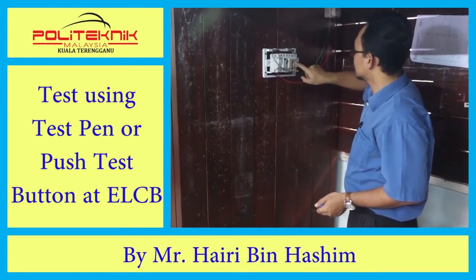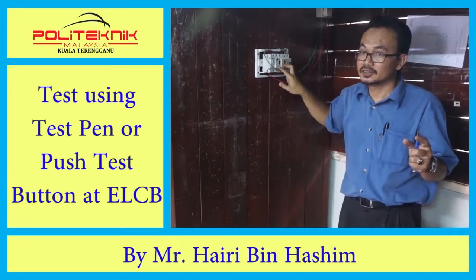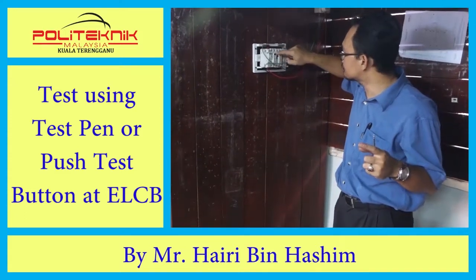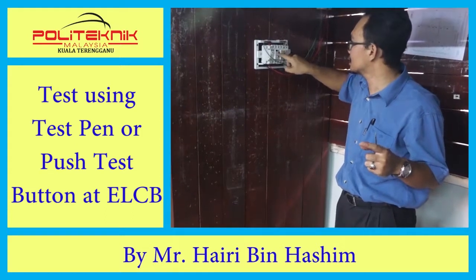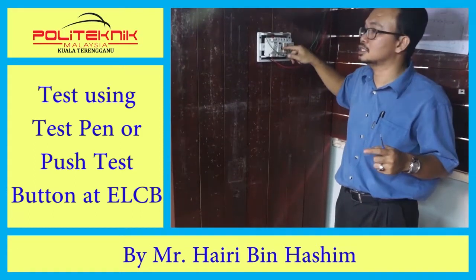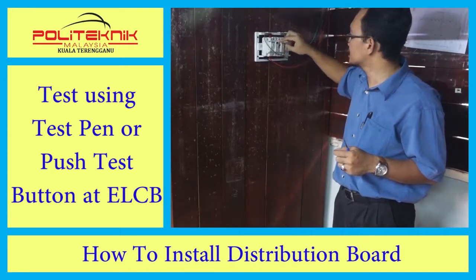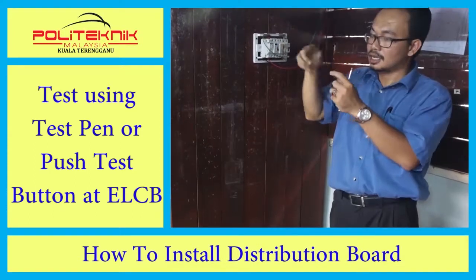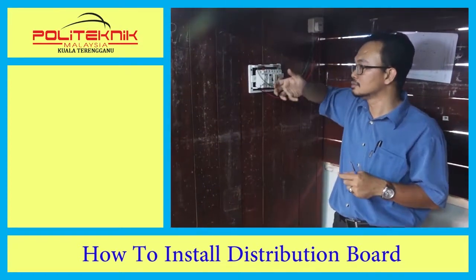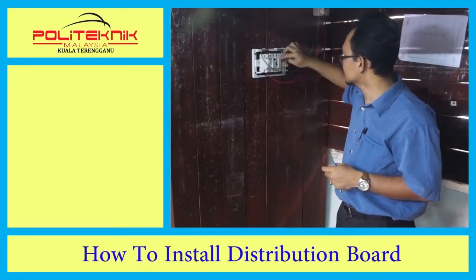The second test is to test whether this ELCB is in good condition. You can try this at home. When you press the test button here, the symbol of T, the switch for the ELCB will trip. Understood? So this means the ELCB is okay, because the test is shorting the current through the ELCB when the current is over the limit for the ELCB, so it will reject the current. Okay, here is okay.